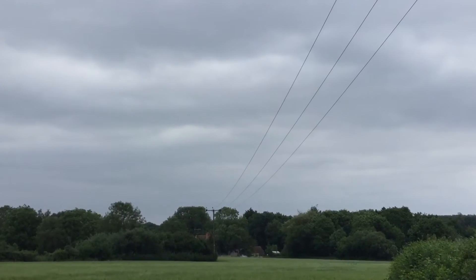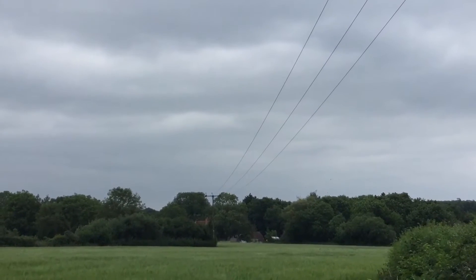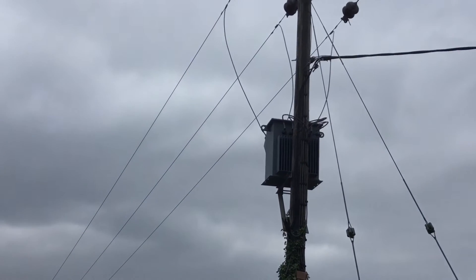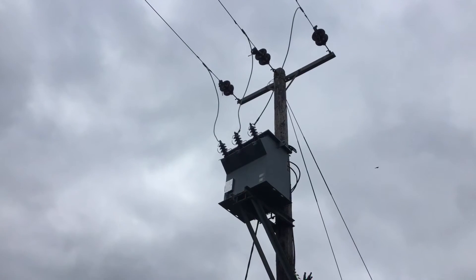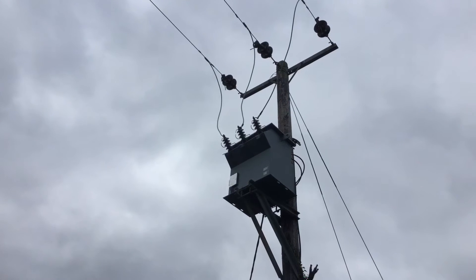These are three overhead bare conductors — all line conductors at 11,000 volts. They are connected in Delta, so there is no neutral at this stage. They are terminated into local transformers mounted on wooden poles where the voltage is changed.